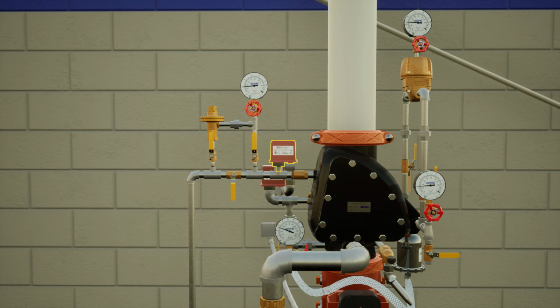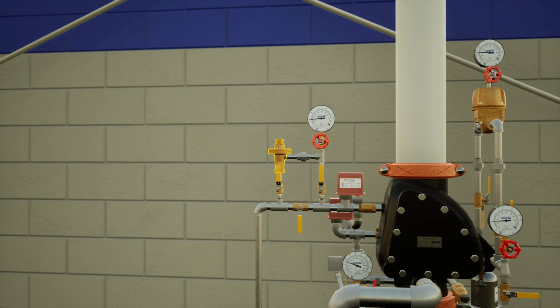Following the loss of air pressure, the low air supervisory alarm is activated. The lowered air pressure will cause the air maintenance device to open. This may trigger the air compressor to start.